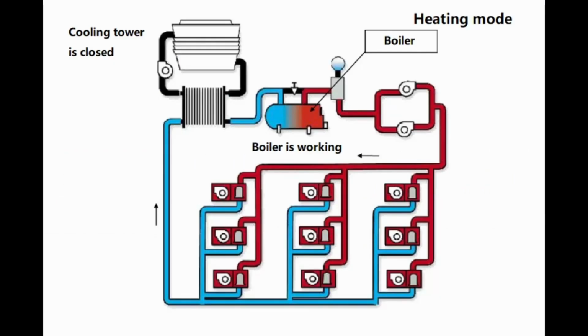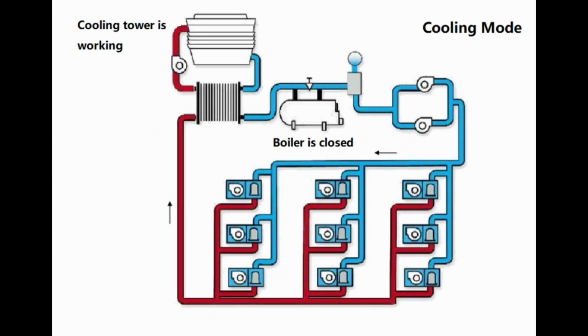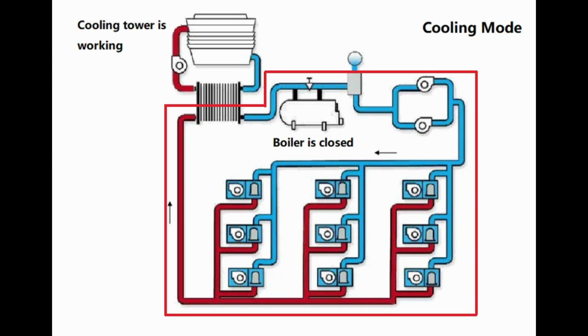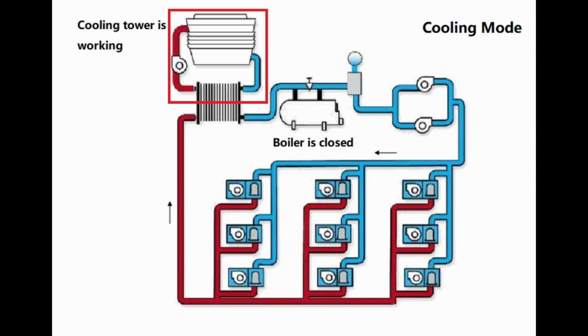The water loop will also flow through a boiler to raise the temperature of the water in winter, and a cooling tower to lower the temperature of the water through evaporation in the summer. The loop should be kept between 60 and 80 degrees. The cooling tower can be closed loop, where the building water loop flows through a heat exchanger, either in the cooling tower or in a mechanical room nearby. The water in the building loop is never exposed to the outside air, but tower water will circulate across that heat exchanger to absorb heat and then be pumped outside and sprayed over the honeycomb-shaped fill inside the cooling tower to take advantage of evaporative cooling.